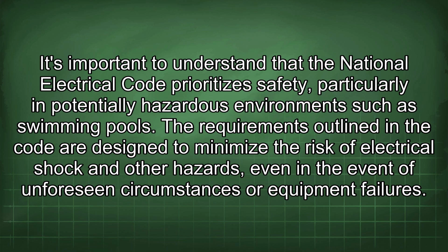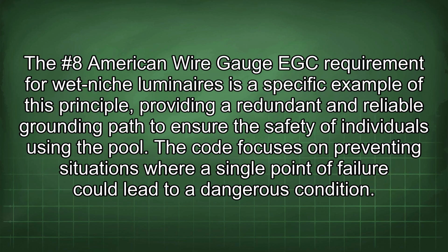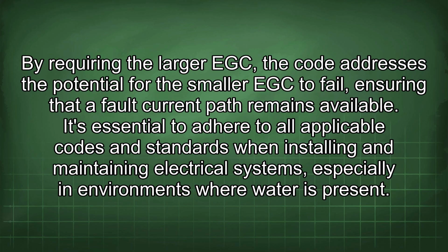It's important to understand that the National Electrical Code prioritizes safety, particularly in potentially hazardous environments such as swimming pools. The requirements outlined in the code are designed to minimize the risk of electrical shock and other hazards, even in the event of unforeseen circumstances or equipment failures. The #8 American wire gauge EGC requirement for wet niche luminaires is a specific example of this principle, providing a redundant and reliable grounding path to ensure the safety of individuals using the pool. The code focuses on preventing situations where a single point of failure could lead to a dangerous condition. By requiring the larger EGC, the code addresses the potential for the smaller EGC to fail, ensuring that a fault current path remains available.